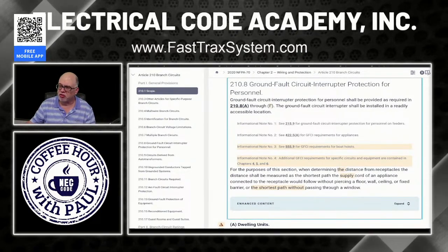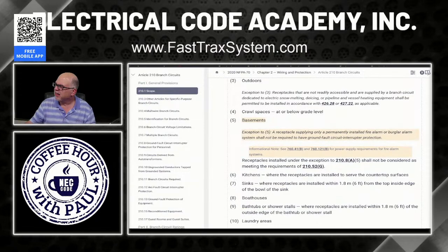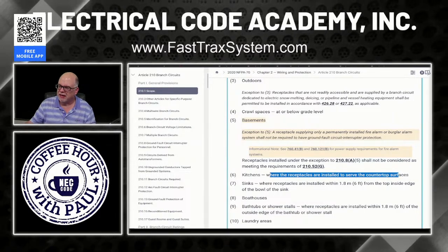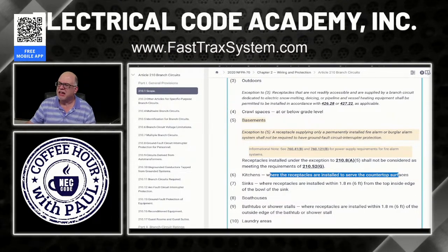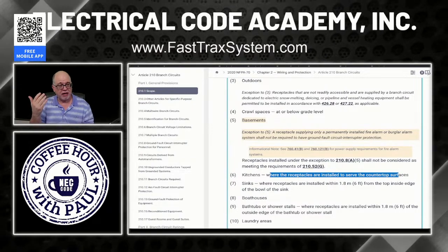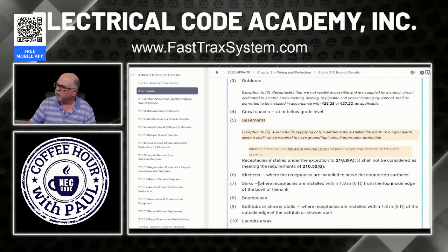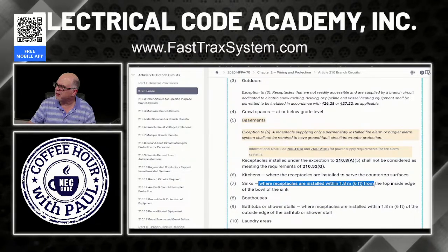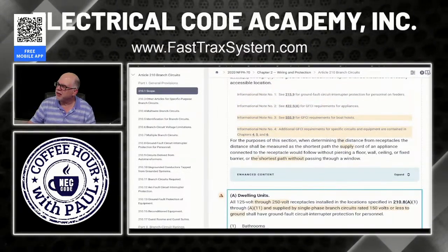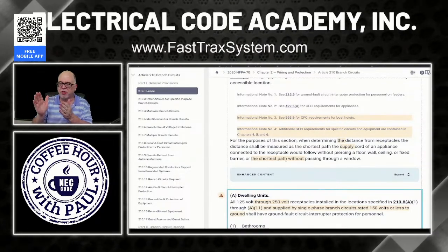Now, as far as the dishwasher is concerned, 210.8(A)(6), just so you can see that right here. Here's A6. And this is what it's talking about, where receptacles are installed to serve the countertop. Okay, that's true. And then 422.5(A)(7), that has to do with the dishwasher specifically, because it's 422, so it's under appliances, right? But I want to draw your attention, again, to the sink. Where receptacles are installed within 6 feet of the top inside edge of the bowl or sink is going to require GFCI protection. And when it comes to this measurement, no longer does a door break that measurement, whether it's a cabinet door or whatever, that's gone now.